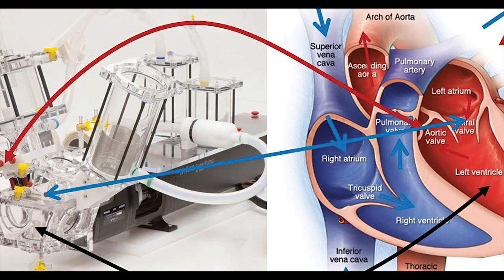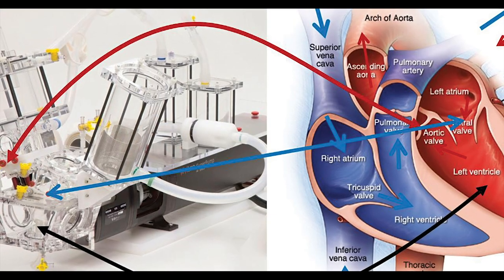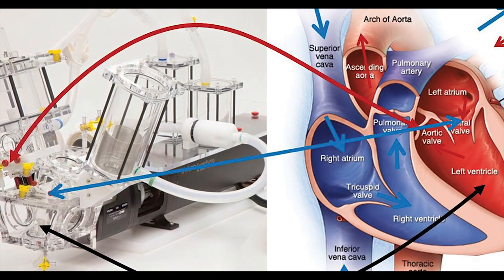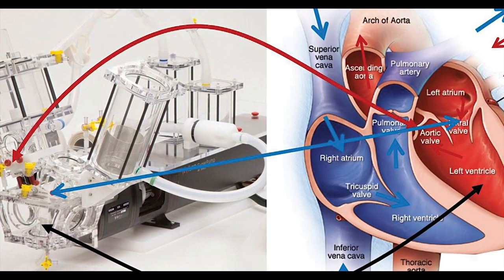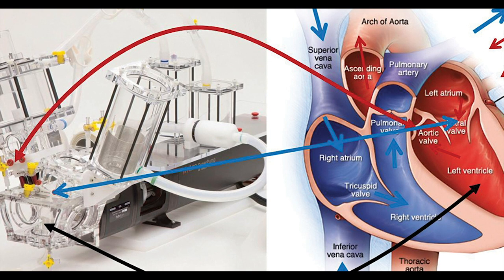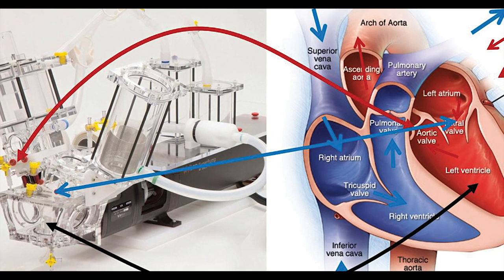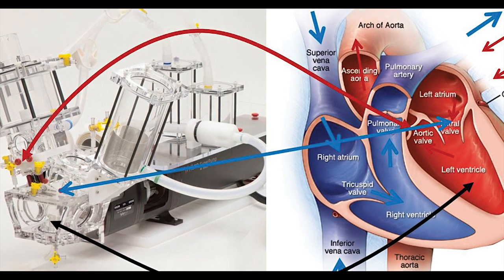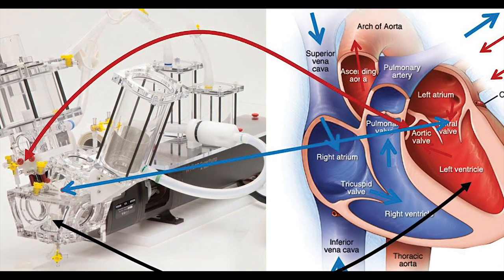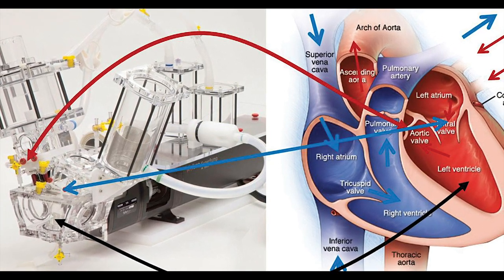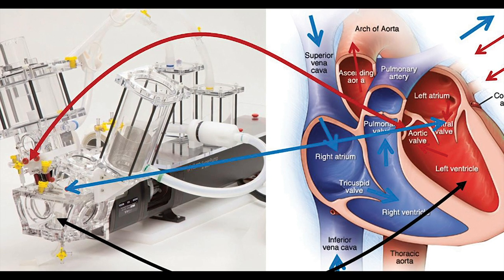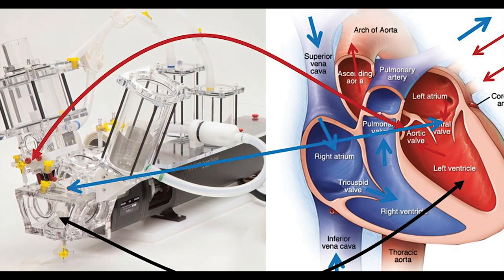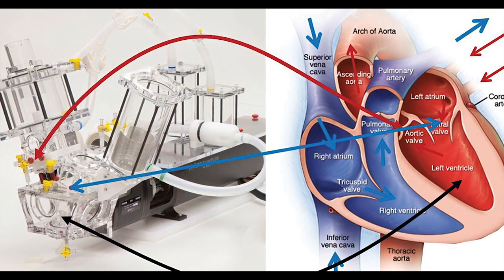Adding the model heart to the super pump creates the pulse duplicator system with a physiological atrium, ventricle, and arterial outflow. The pulse duplicator system replicates one half of the human heart.